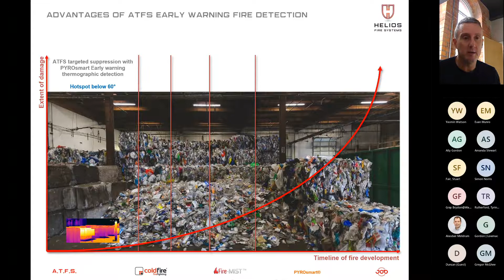First, I'll promote my product because we're the earliest: ATFS targeted fire suppression with PyroSmart early warning thermographics. We are at the very bottom of this damage curve, and at the earliest timeline of fire development. We don't need smoke, vapor, or flames to activate - we just need a hotspot. We can trigger from one degree above background temperature as a pre-alarm or full alarm, though obviously we won't do that. Thermographics are the most advanced way of detecting deep-seated fires within waste piles or baled storage areas. So that's where we are - we have thermographics.